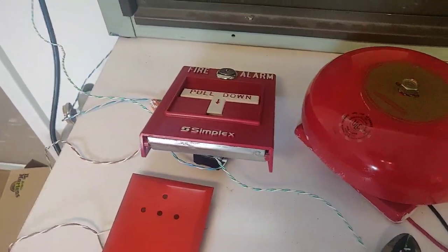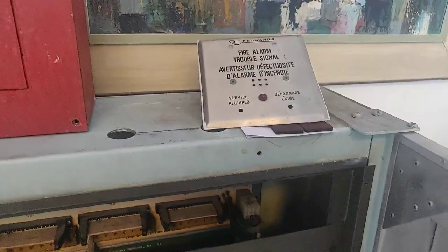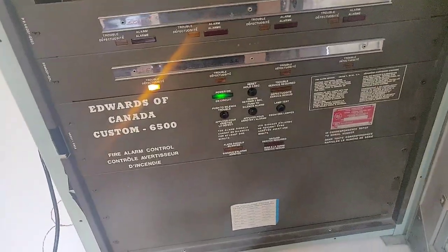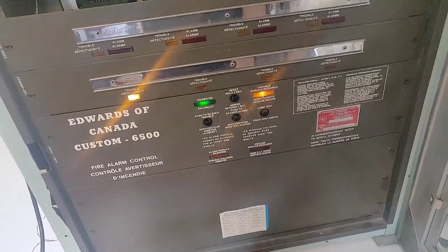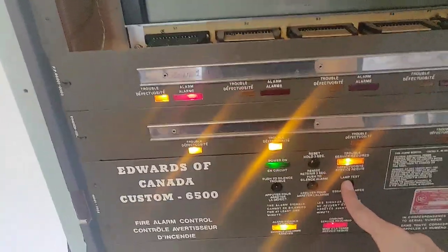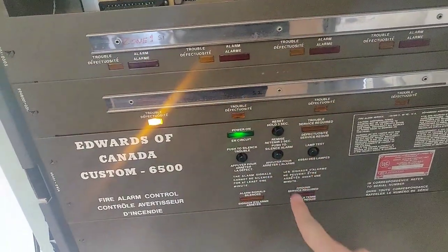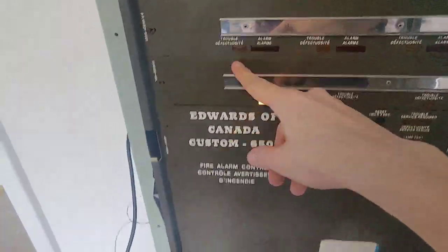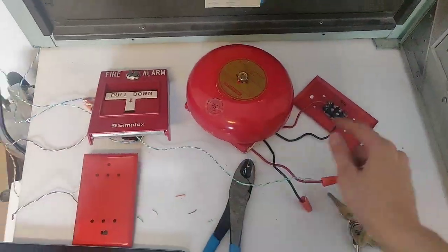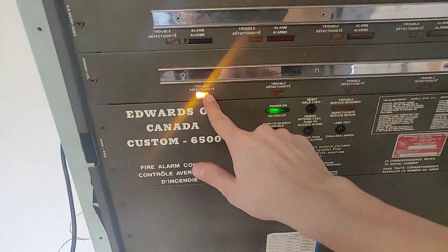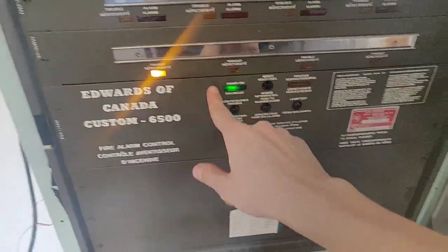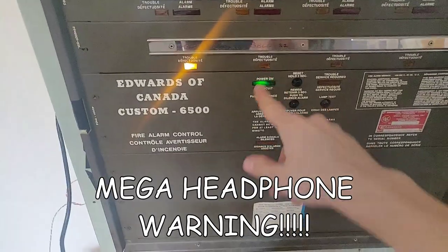Alright, so we have our initiating zone, our bell zone, our trouble alarm and our annunciator. So this is exactly how you'd find the system set up in a working environment for the most part. Let's perform the lamp test. See those bulbs? All the bulbs are working. So no trouble here and no trouble here on account of our closed circuits. Bell 1 has a trouble because nothing is connected to it. I'm only using bell 2. So let's pull the pull station.